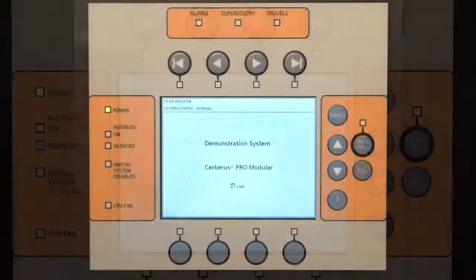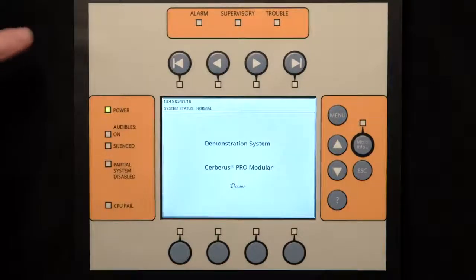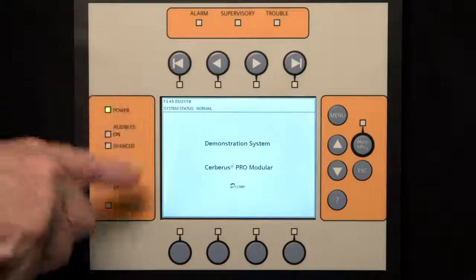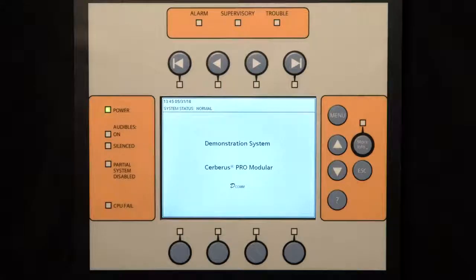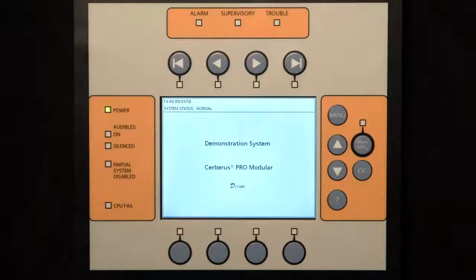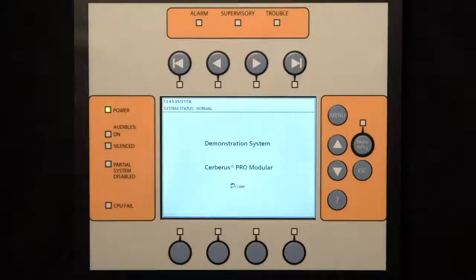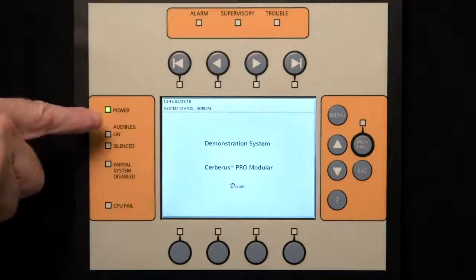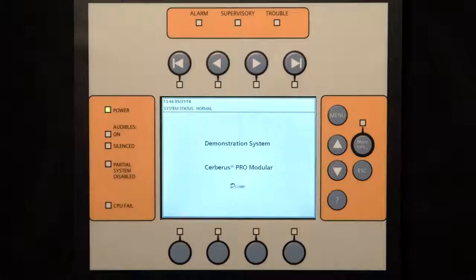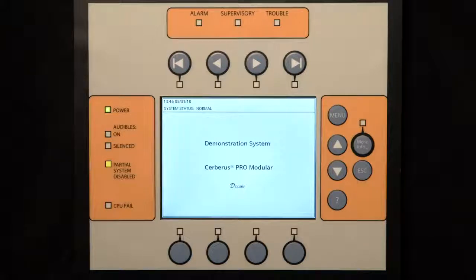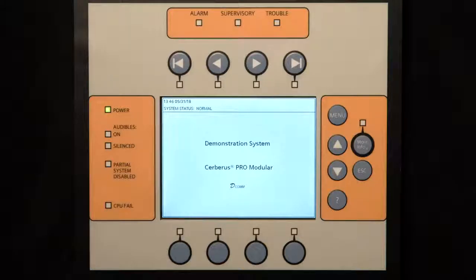The system status LEDs show basic system operation. These status lights include display power, state of the system audibles, horns, strobes, and speakers, and if any part of the system is turned off or disabled, and if the main fire alarm computer is functioning properly. The power LED will glow steady green to indicate that the AC power is on and will flash when the system is operating on batteries. The partial system disabled LED will glow steady yellow to indicate that the device is disabled.